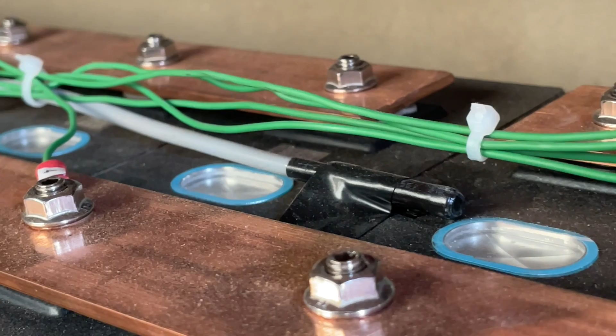If any of those parameters are off, it reacts, and it also balances the cells. So once it gets to a certain voltage, it will start balancing. This is a top balancing system, because the way we expect Jonathan and Ashley to use this is solar's going to come pouring in, fill up their battery, and they're going to hopefully, if we've designed the system correctly, sit in the top half of the battery most of the time. And what that'll do is extend the life.